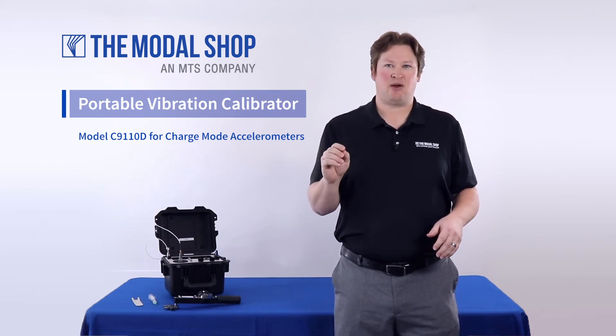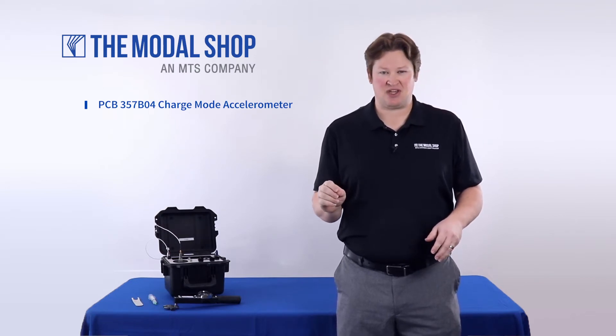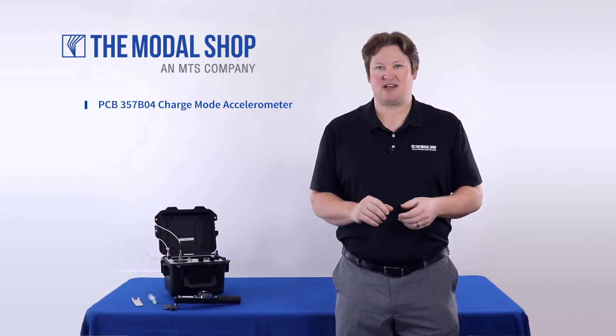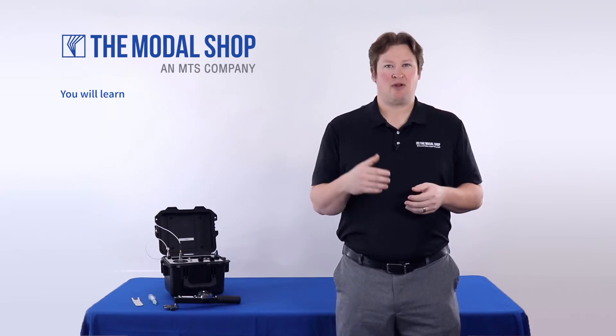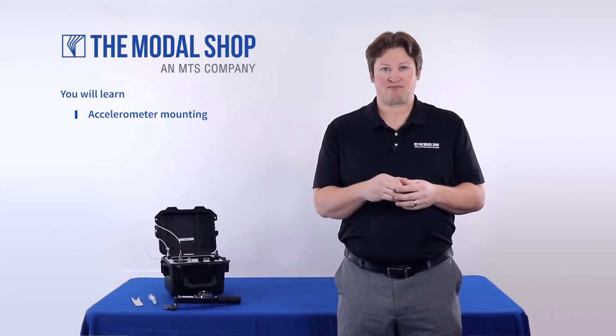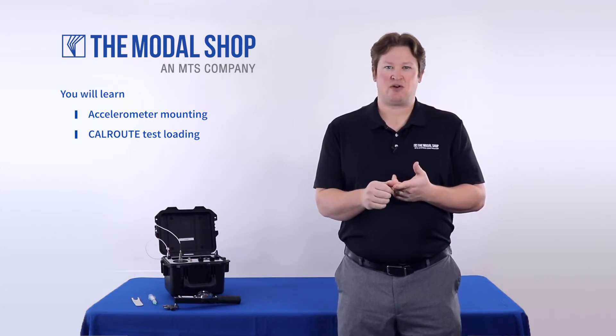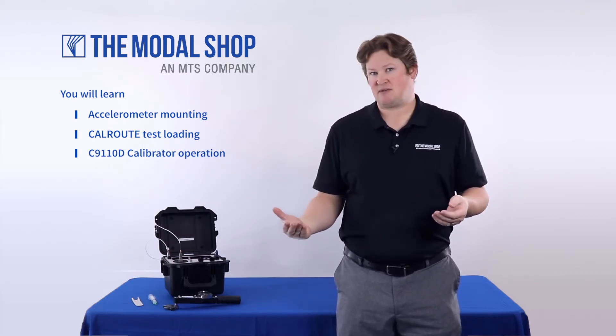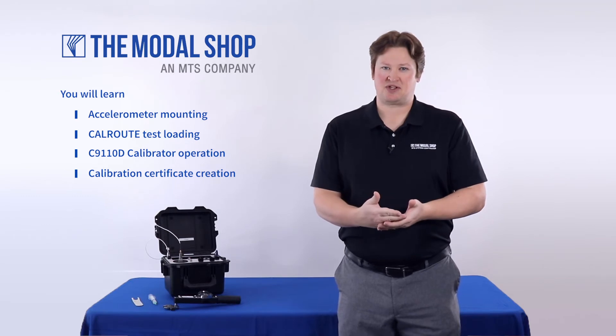Today we're going to calibrate a PCB 357B04 single-ended 10 picocoulomb per g charge mode accelerometer for the test and measurement market with a plus or minus five percent tolerance to nine kilohertz. In this video you will learn how to mount the transducer and connect it to the C9110D portable vibration calibrator, how to load a cal route — a pre-programmed step sine test with a pass/fail notification after each test point — how to operate the C9110D and execute the test saving test points to memory, and how to create a calibration certificate.